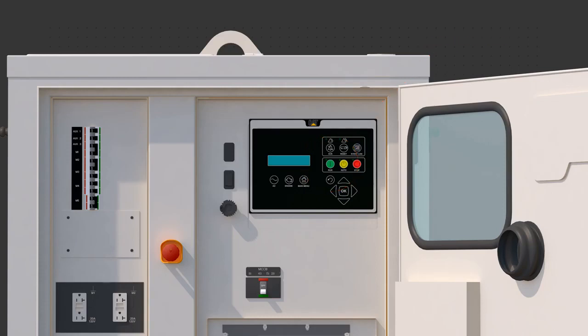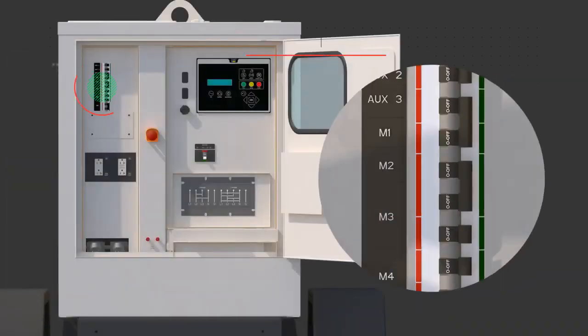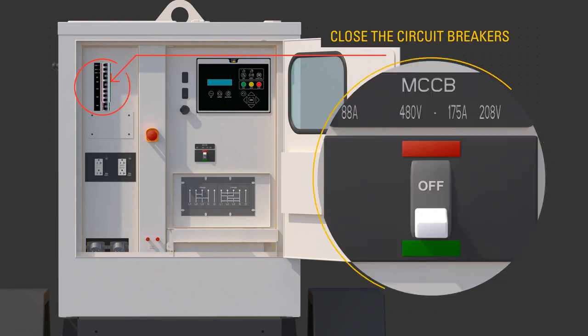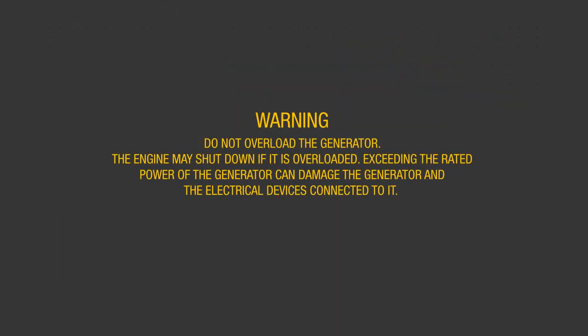Allow the engine to reach operating temperatures, about 3 minutes. Close the circuit breakers necessary to supply customer loads. Warning: do not overload the generator. The engine may shut down if it is overloaded. Exceeding the rated power of the generator can damage the generator and the electrical devices connected to it.